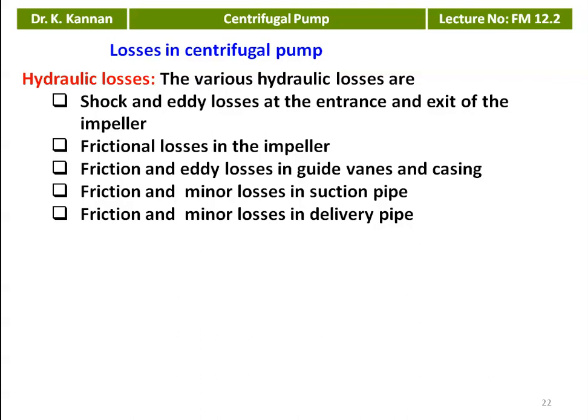There are friction and minor losses in the suction pipe, including losses when water enters suddenly or passes through a suddenly enlarging portion of the flow passage. In the suction pipe, we have a valve, pipe fittings, and a lengthy pipe, so both minor and major losses must be calculated. Similarly, friction and minor losses occur in the delivery pipe due to pipe fittings, sudden enlargement, or contraction. All these are called hydraulic losses.